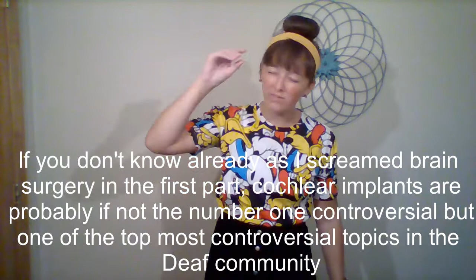So the transmitter is attached to a magnet that is inserted behind the skin. So open the skin, shove it in there, on the skull. The skull is slightly drilled. They're drilling into your skull in order to make a depression about the depth of a quarter to fit a magnet there. So the external hearing aid, along with a magnetic field, is attracted to the magnet embedded under the skin behind the ear. All of this just sounds so painful to me. I don't know about you. So this allows the recipient to take off or put on the device at ease, at their discretion.